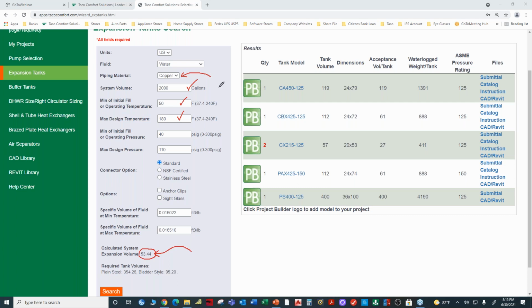So in other words, the copper piping in the system also expands as a function of temperature. So the fluid is actually expanding a little bit more than the 53.44 gallons, but the copper pipe is taking up some of that expansion because it's heating up and it's getting physically larger. Now we're going to ignore the plain steel tank for a moment and just focus in on a bladder style tank. In the bladder style tank, the steel container needs to be 95 gallons. And the acceptance volume is the same as the expansion volume. That means that the bladder has to accept 53.44 gallons.